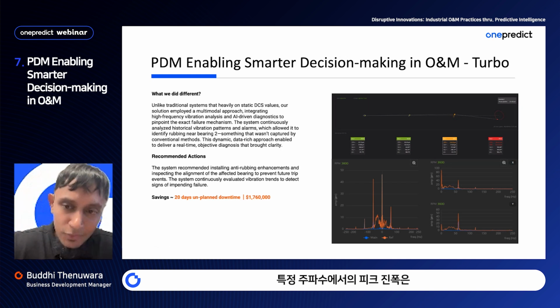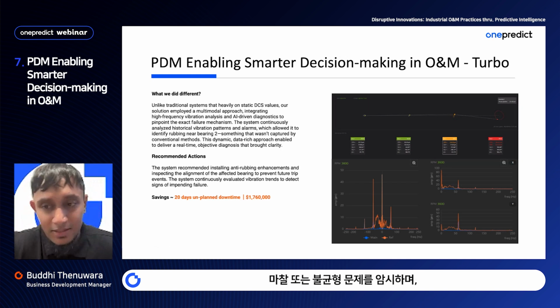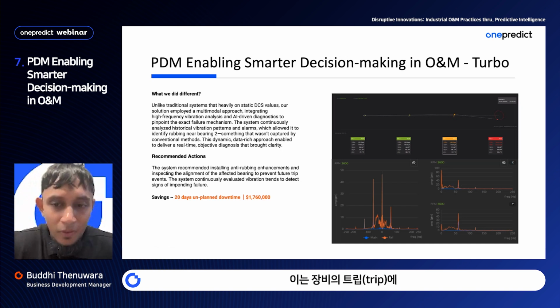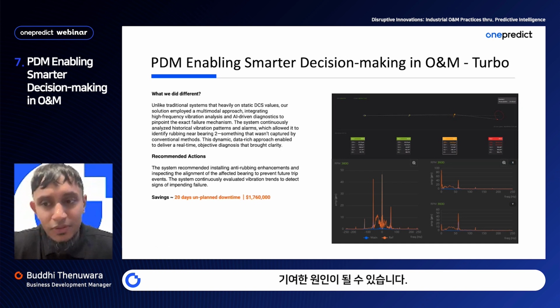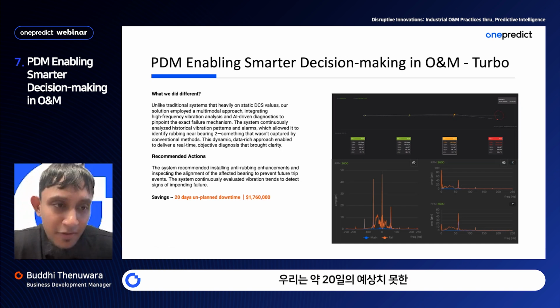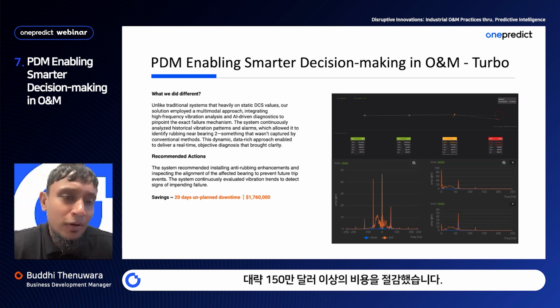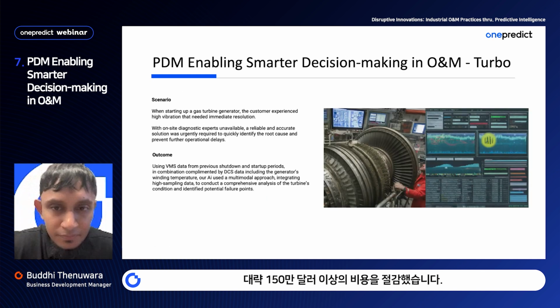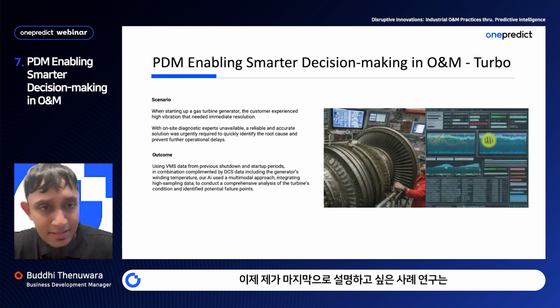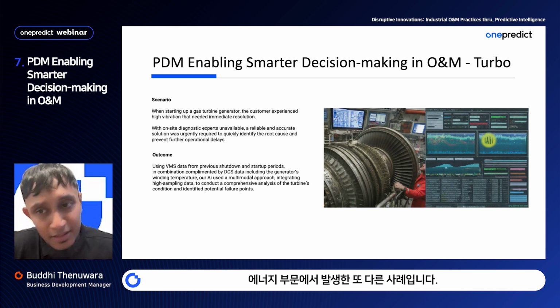The peak amplitudes at certain frequencies suggested potential rubbing or unbalance issues that contributed to the equipment's trip. We were able to save around 20 days of unplanned downtime and a little over 1.5 million in savings. This is my last case study that I wanted to walk you through as well. This is another case study from the energy sector.